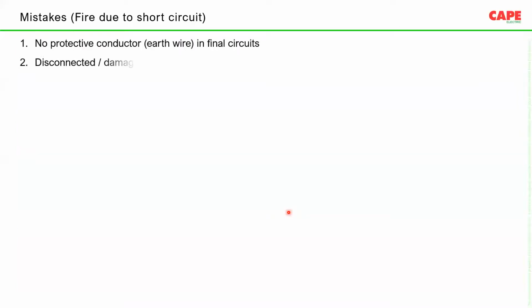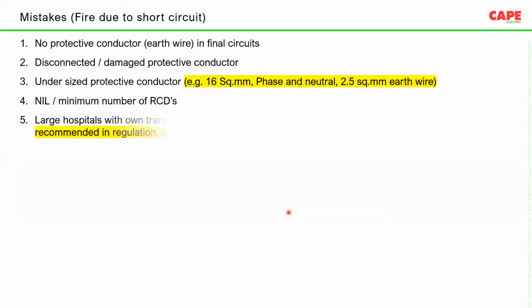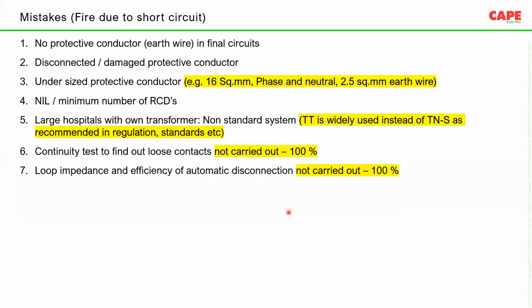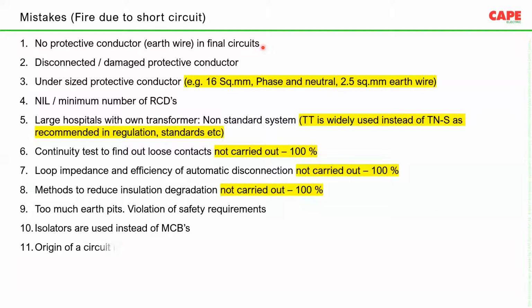So what is required? The general mistakes: fire due to short circuit, there is no protective conductor, there is no earth wire in the final circuit. From the switch up to the socket, only the phase conductor and the neutral conductor go, and there is no earth wire. And if there is no earth wire, in case of earth fault, you should understand what is going to happen.